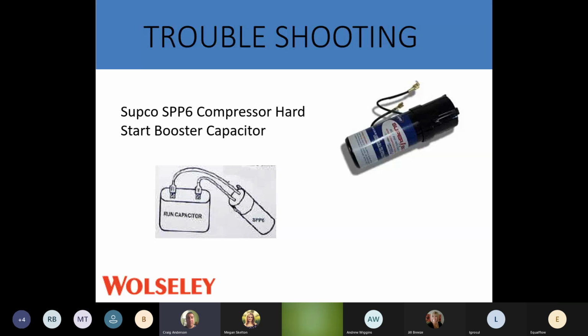But this little device, for the price of them, $35 or whatever they are in that range, could save a customer another couple years on their air conditioner. Or that unit just needs a little bit to get up and go. Real long line lengths, 50, 80 feet, stuff like that, good idea to have one of these on the compressor. It's working hard. Throw one of these on. Get you out of a good jam. I know when you get busy, you're doing 10 to 12 calls a day. So this could save you a lot of time for a customer. Just get that compressor going and get off to the next one.